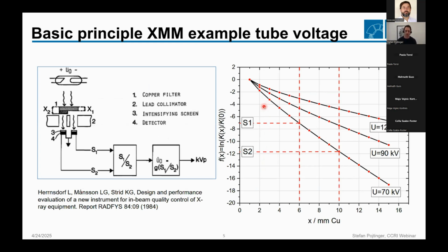So in the actual detector unit of an XMMs, you don't have one silicon diode, you have multiple silicon diodes. For example, this could be one silicon diode, this could be the other silicon diode. And then the idea is that you have different pre-filters inside of the detector unit, so each silicon diode will be filtered differently. And then you don't look at the signal of a single diode. You can, for example, look at the ratio of two diodes. Because of the different filtrations of the diodes, you will get different results. And if you look at the ratio, you will see that this ratio will change, of course, with the filtration thickness, but also with the energy, or the tube voltage, at a real device.